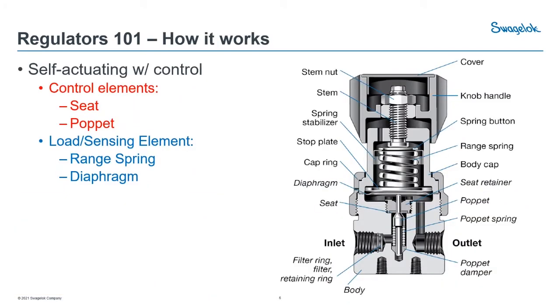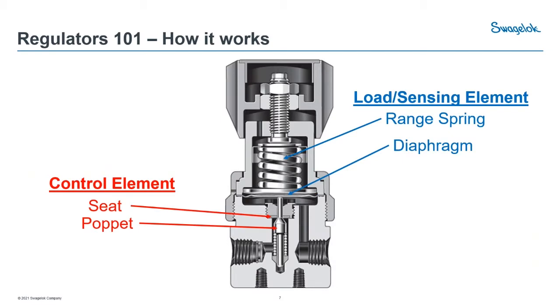How exactly does a regulator work? This is a self-actuating with control device, and if you see on the right there are a bunch of different moving parts that make these look pretty complicated. But today we're going to focus on the four control elements that mainly work for the regulator function. We have our two control elements — the seat and poppet, located on the lower half of the regulator — and on the loading and sensing element side, we'll focus on the range spring and the diaphragm.